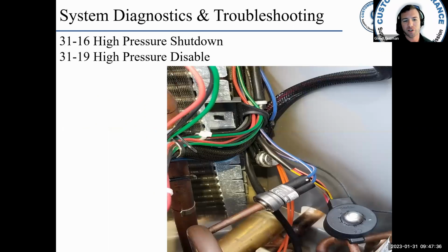3116 high pressure shutdown and 3119 high pressure disable. High pressure switch opens at 670 psig. 3116 should never occur because the discharge transducer high limit is much lower than the high pressure switch trip point. If you have an active 3116, inspect the wiring of the high pressure switch. You can see the high pressure switch here. Check your wires, make sure your wires are not pinched. It goes back to the VFD. Make sure that the plug at the VFD is secure, that the wires are in the plug properly. Again, 3116 should never occur. Your discharge transducer should shut the unit down first before the high pressure switch trips.